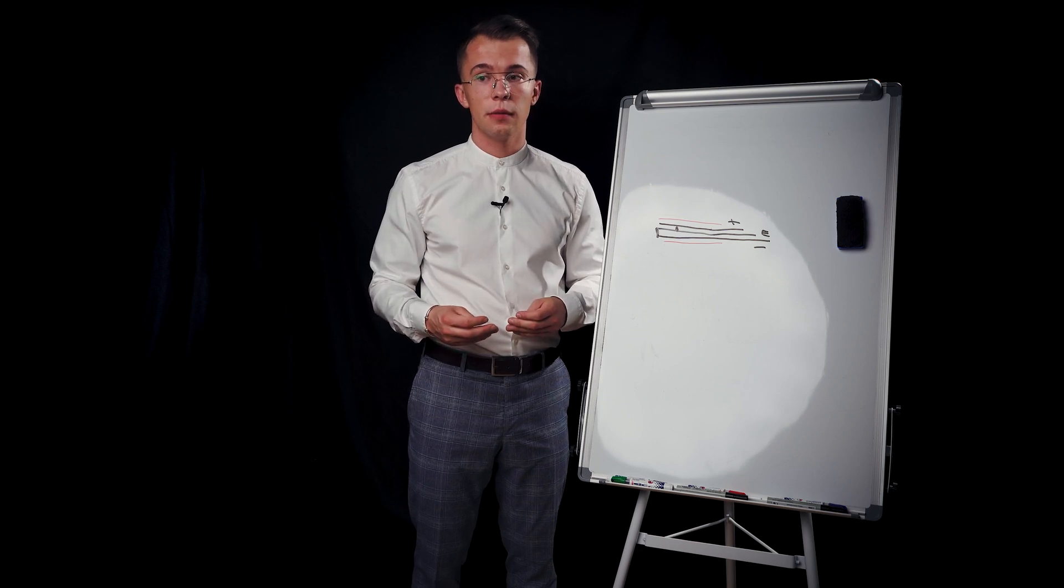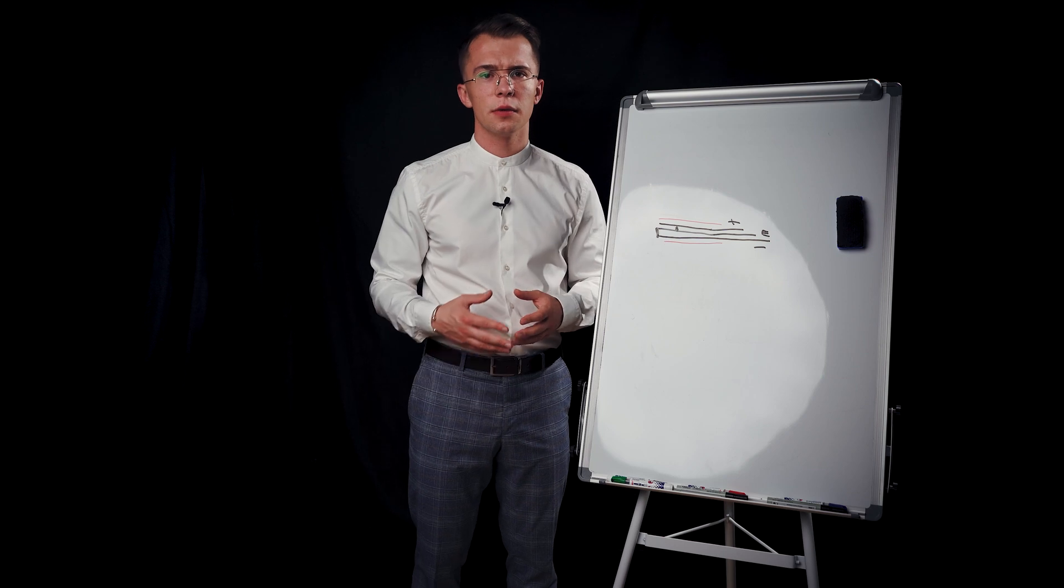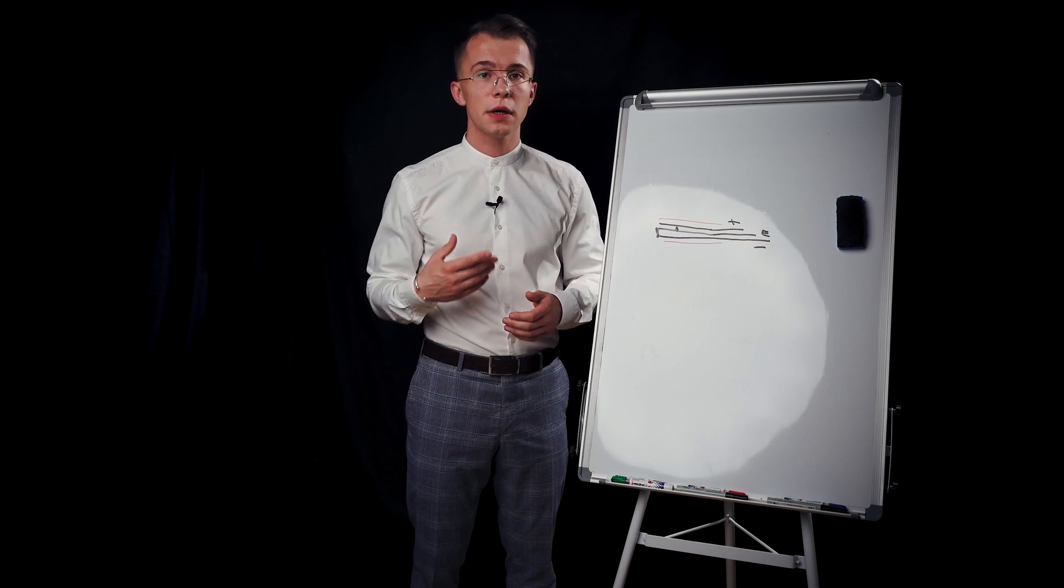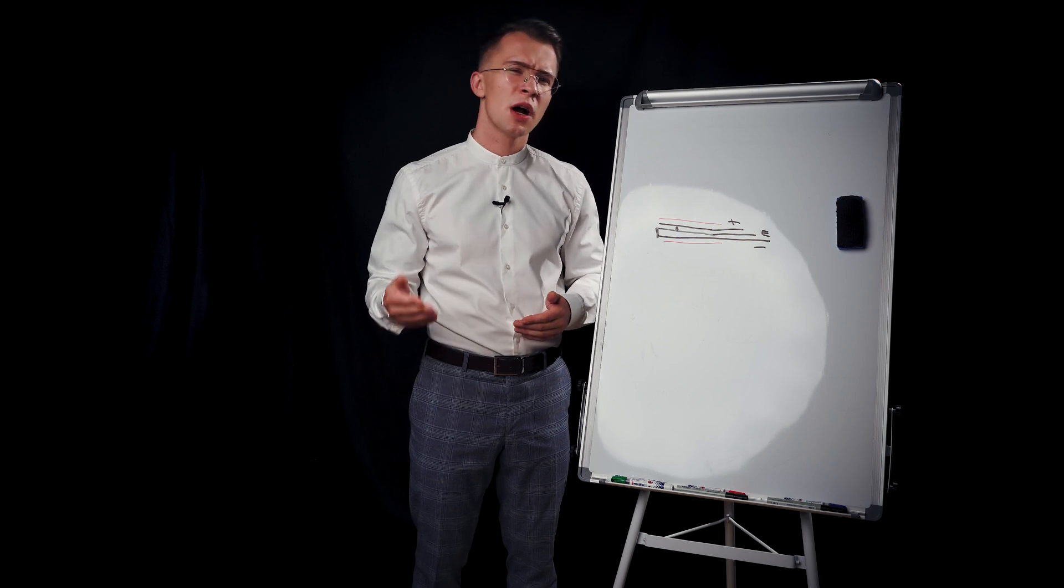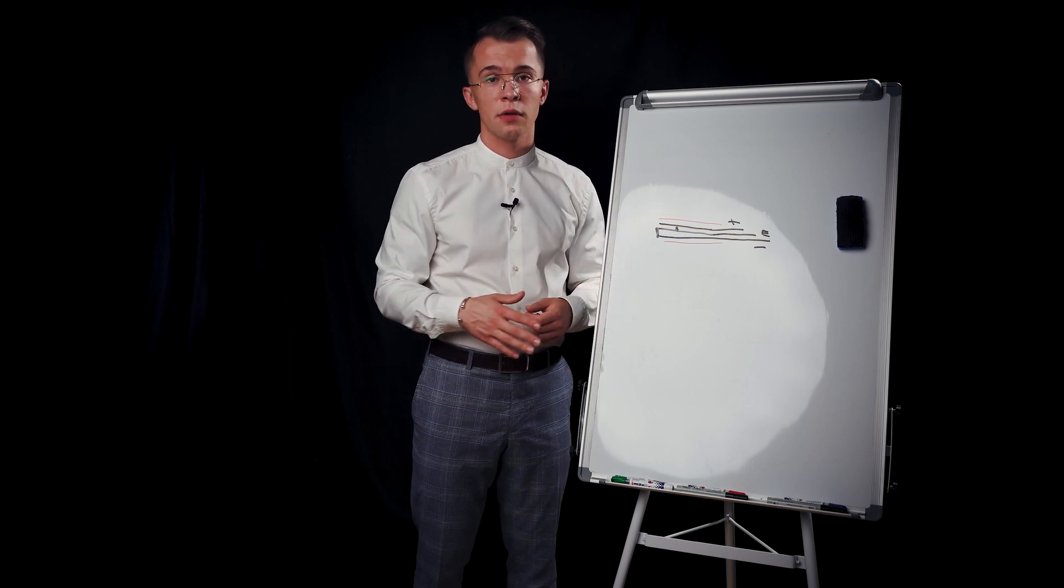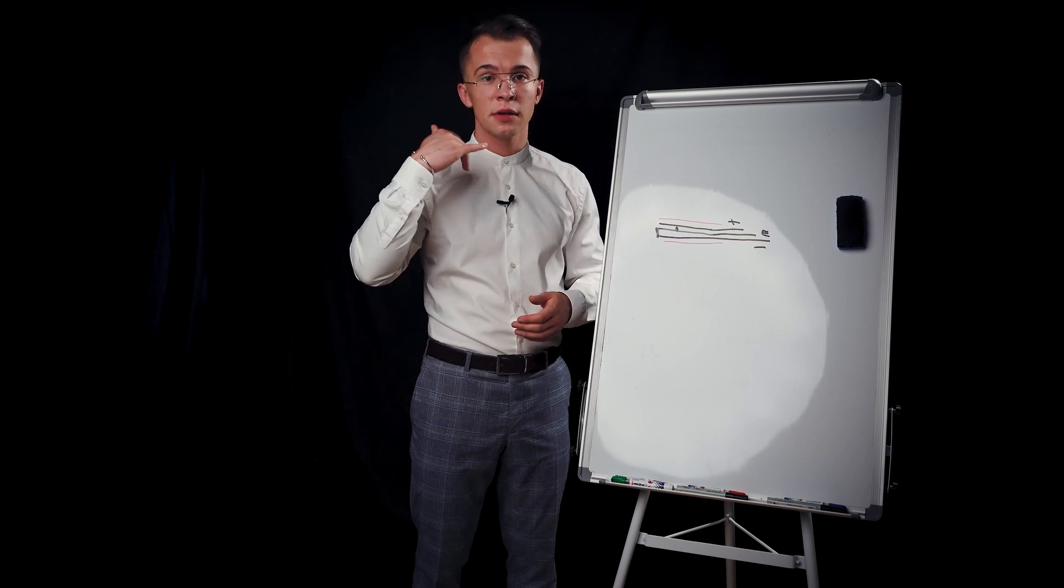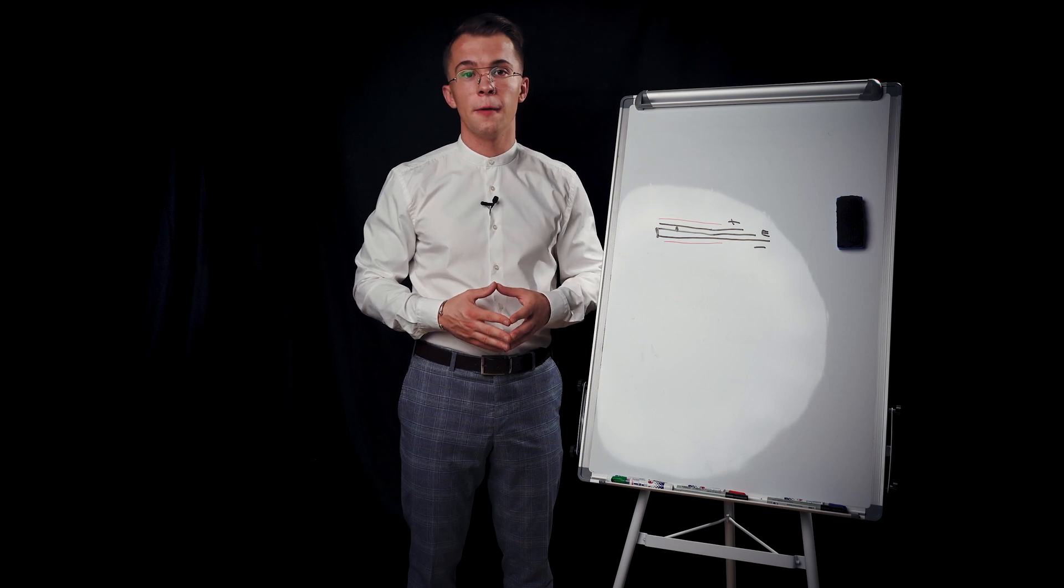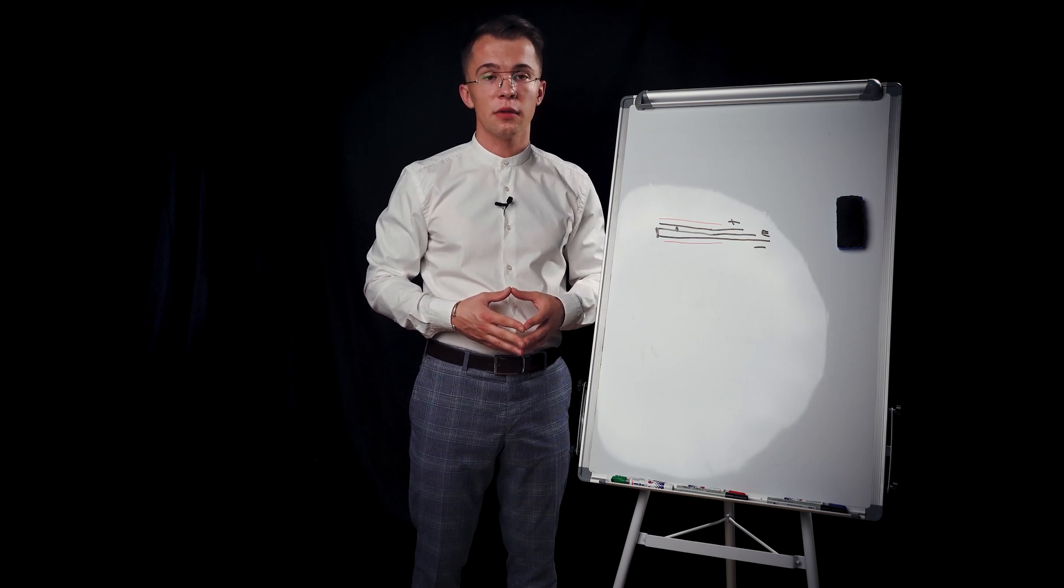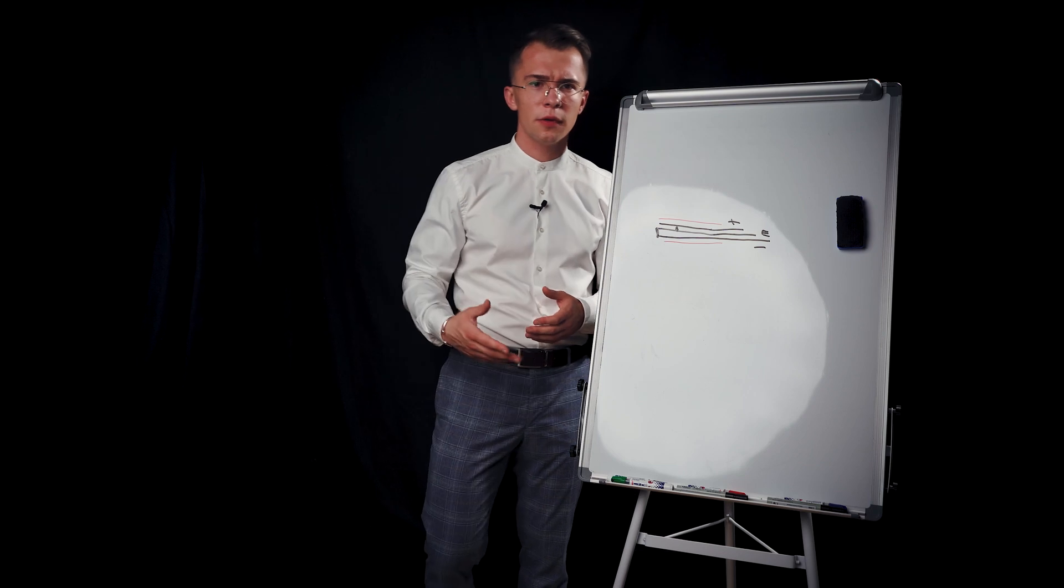This is how you troubleshoot the earth fault. Now, practically what might happen is that the earth fault is building very slowly, and this happened to me also in the past. This particular fault might cost you a couple of visits on site because you're connecting something back and the fault disappears and doesn't come back within 10, even 20 minutes, even half an hour sometimes. You're leaving the site and getting a phone call that the earth fault came back onto the system. That's why I said it's one of the most difficult problems to deal with, and sometimes it might cost you a couple of visits.